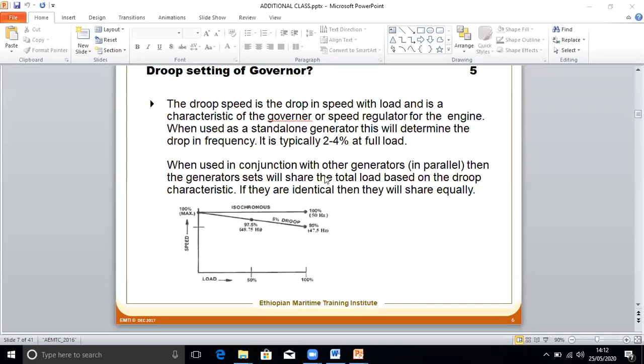So basically, for paralleling, only your voltage, frequency, phase angle, and phase sequence, these four parameters should be the same. Kilowatt doesn't make a difference here. So if you make a higher droop, it can share less load. If you make the lesser droop, it will take more load. Hope these things are clear.